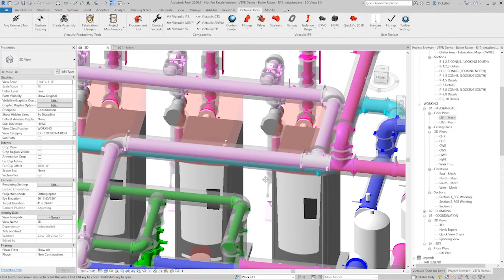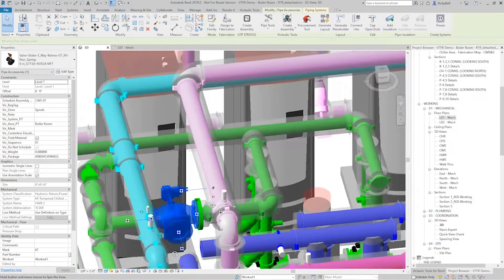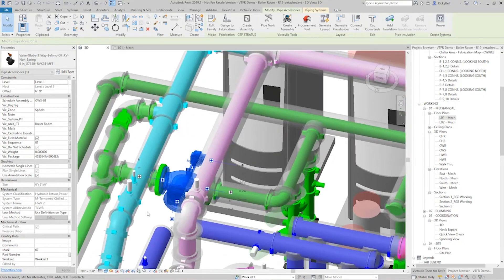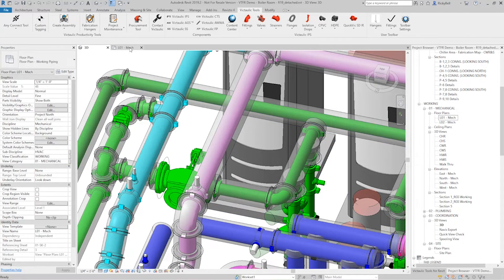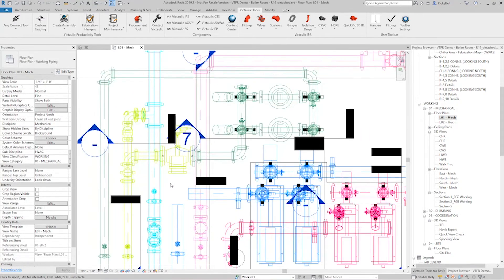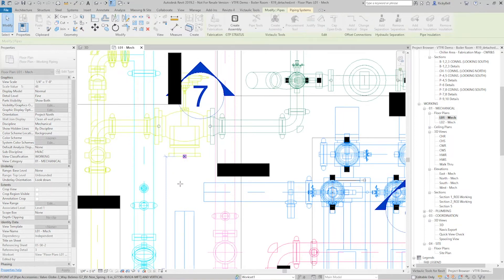Another situation where the Systemizer will come in handy is when you're trying to connect multiple systems around something like a control valve. Revit has gotten a little better with trying to keep systems separate, but it still comes up short from time to time. I'm going to jump into a plan view here. I want to connect this blue line into these green ones — I have a chilled water and a tempered chilled water system — up into this mixing valve. I can use Revit to click and drag that connector in, and you can see it is keeping those items somewhat separate.